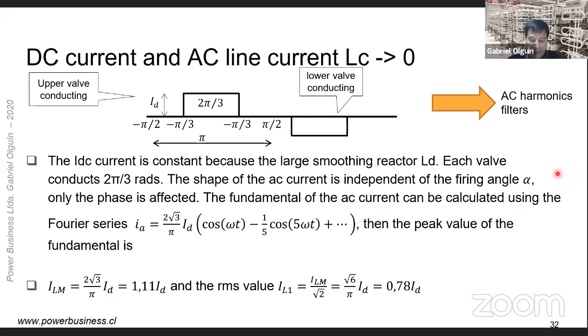The DC current in the HVDC line is constant because of the large smoothing reactor. Each phase of the AC system supplies current to the DC link. The line current in each phase has a square shape because each valve conducts 2 times pi over 3 radians, or 120 degrees. Upper valves feed the positive current to the link, while lower valves carry the return current. The shape of the AC current is independent of the firing angle. Only the phase is affected by the ignition delay, which in turn affects the power factor of the converter, because of the phase shift between the fundamental of the current and the fundamental of the voltage.